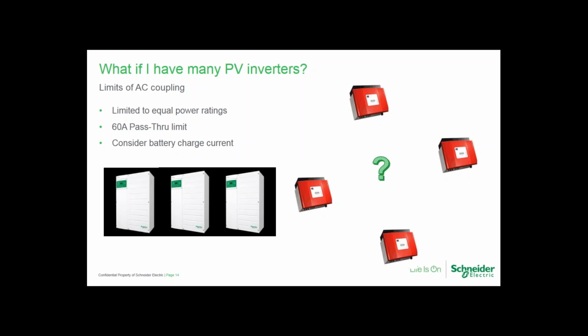Now that said, if you're designing a multi-unit system that is off-grid with a generator, then certainly you could have a situation where your XW system is transferring power at least once a day, maybe even multiple times a day. So that is a situation where you are really going to need to be cognizant of that 60 amp limitation, because you're doing a lot of switching. And when you're passing through more than 60 amps and you're switching many times per day, or even once a day, over time that's going to result in premature wear on the relay. And if the current level is high enough, then it could even weld the relay shut. So we really want to be careful there.